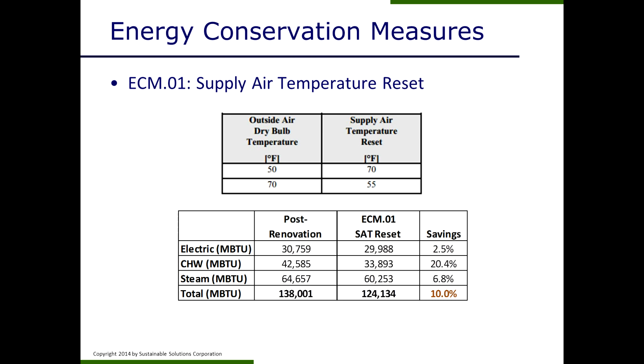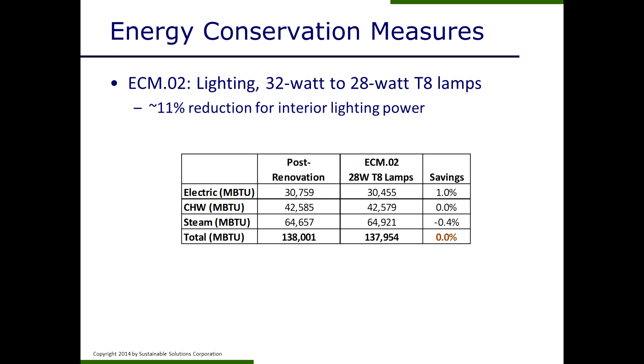Another energy conservation measure that we looked at was converting from 32-watt lamps to all 28-watt lamps, and this basically resulted in an 11% reduction in interior lighting power, because it was almost primarily lit with T8 lamps. You can see there we had a 1% savings in electric usage, but we took a little bit of a hit in steam usage because now that extra lighting isn't heating the space, so there's a little bit extra steam required for heating the spaces. But overall, there would be a cost savings associated with that, because electric for this building is much more expensive than steam.